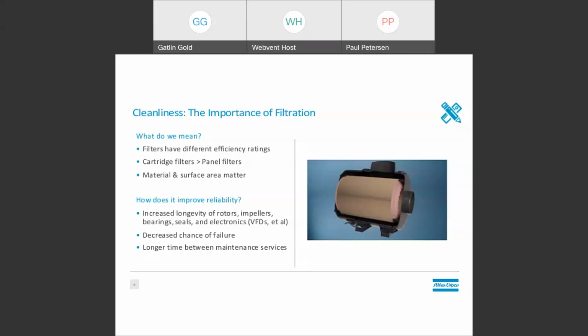Now, for something like a multi-stage centrifugal that has large internal tolerances spinning at 3,600 RPM, it's not really much of a problem. But for a high-speed turbo blower rotating at 30,000 RPM, those particles can cause significant wear over a very short period of time. If that turbo blower is using sensitive airfoil bearings, the damage caused by filter bypass could be swift and catastrophic. Typically, a more efficient filter has a larger pressure drop. However, by increasing the surface area of the filter, the pressure drop is reduced.